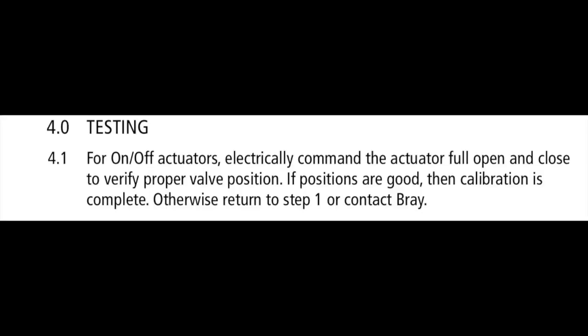For on-off actuators, electrically command the actuator full open and close to verify proper valve position. If positions are good, then calibration is complete. Otherwise, return to step 1 or contact Bray.